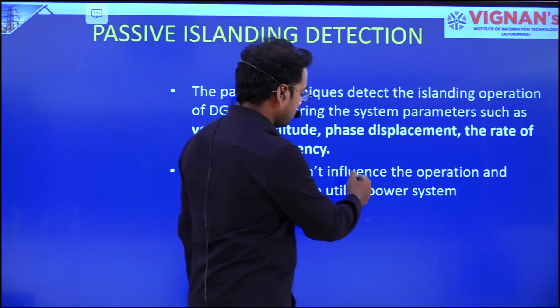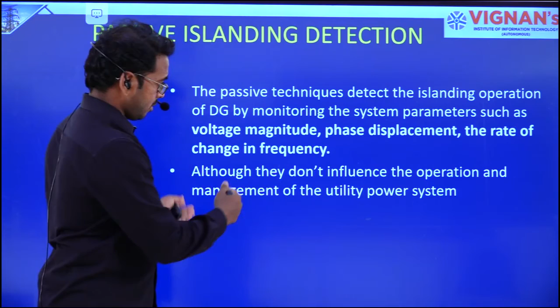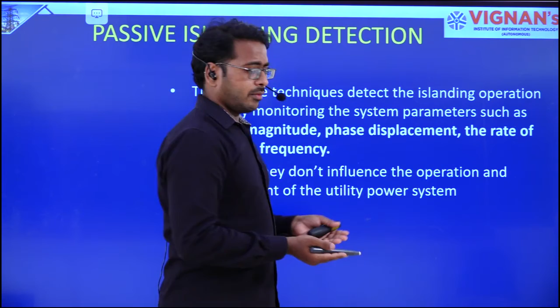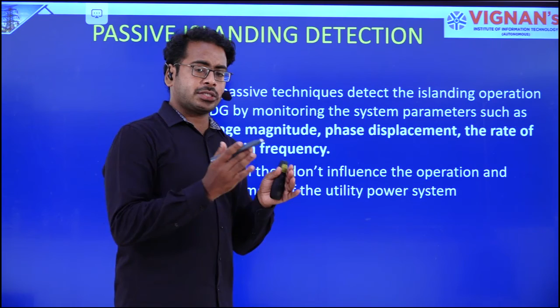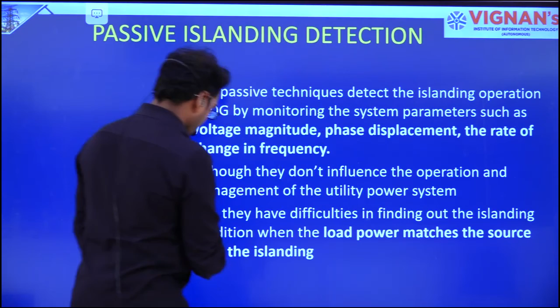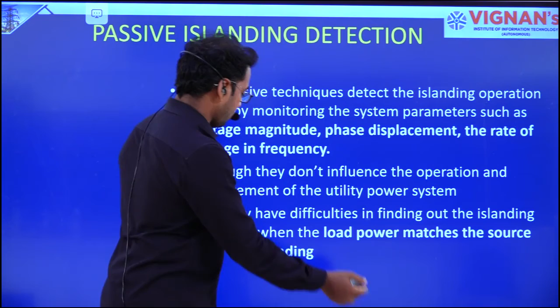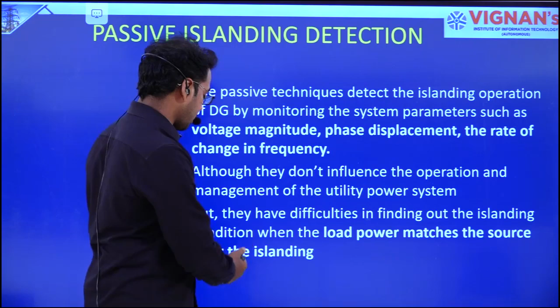They don't influence the operation and management of the utility power system, because we are just measuring parameters at PCC and deciding whether it is in islanding condition or not. But they have a difficulty in finding the islanding condition when the load power matches the source after the islanding. In this condition, when the load power matches the source, it is unable to detect whether it is an islanding or non-islanding condition. That is the issue.